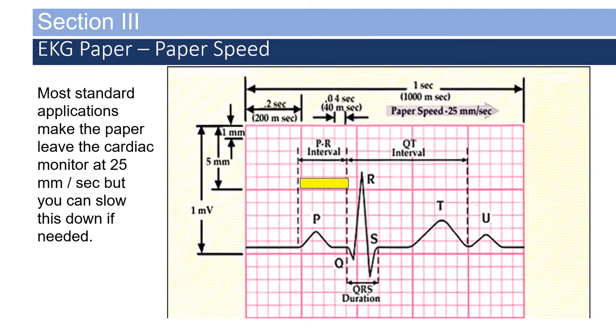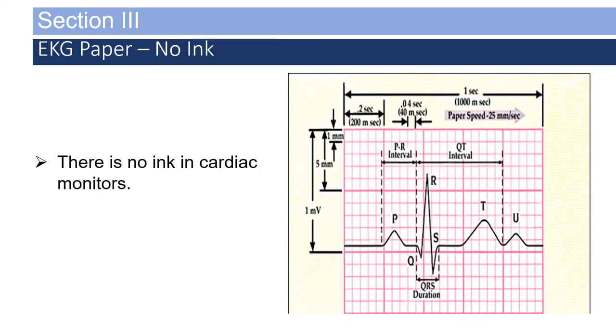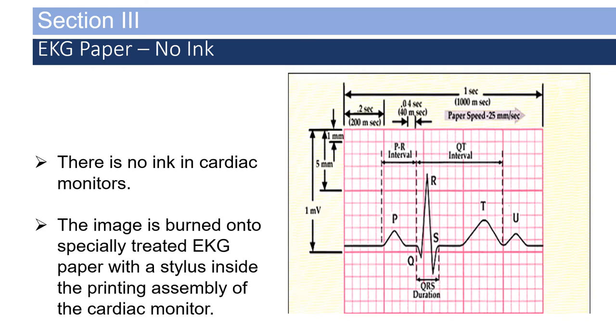For most cardiac monitors, the cardiac paper leaves the monitor at approximately 25 millimeters per second, but you can slow it down or speed it up if needed. Cardiac monitors do not contain ink or ink cartridges — the image is burned onto specially treated EKG paper with a stylus inside the printing assembly.